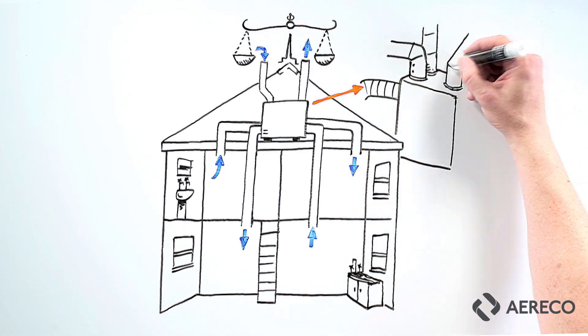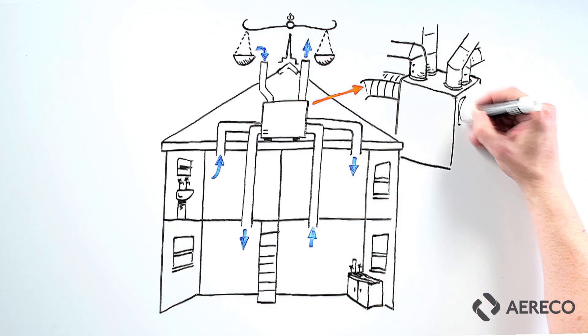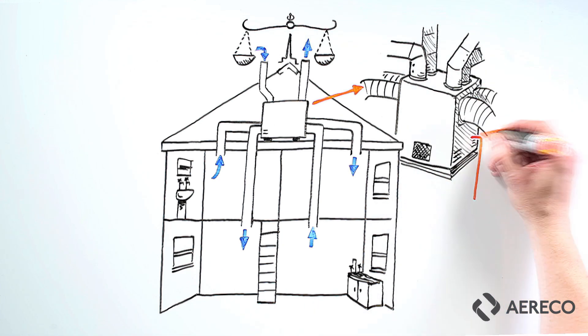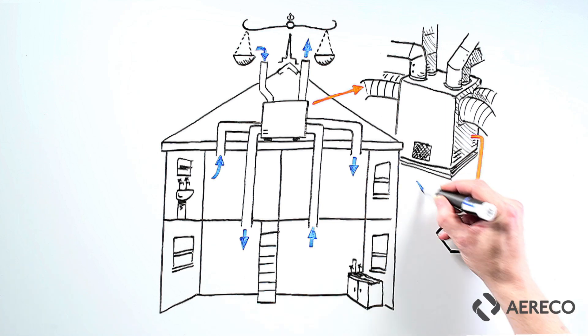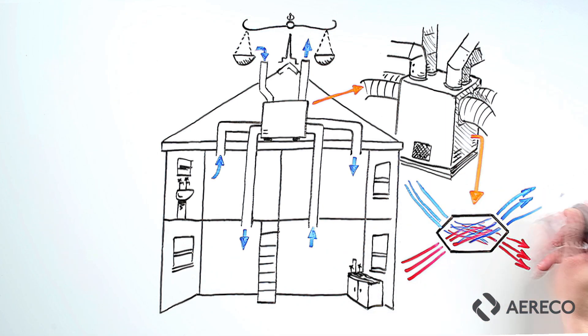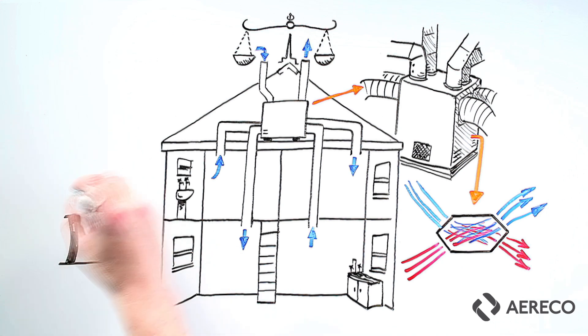An MVHR system is designed to not only provide good indoor air quality like the others, but it's also designed to recover heat that would otherwise be lost through ventilation. It does this by passing the stale warm air it is extracting past the cold fresh air it is supplying. This warms the incoming air up. It does this in a heat exchanger within the fan unit.